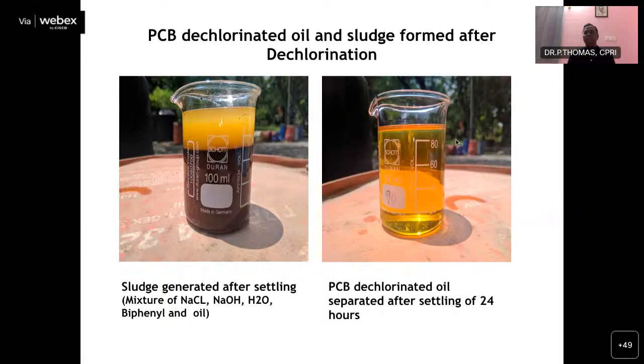So this oil is free from PCB, but it cannot be directly used in a transformer. Further treatment can be done, but even after that, the oil cannot be used in high power transformers—it can only be used in distribution transformers, and of course you have to add some additives.